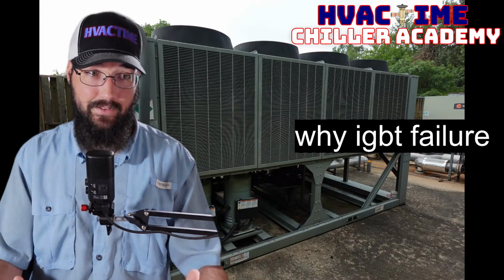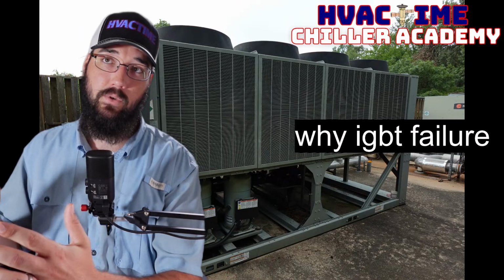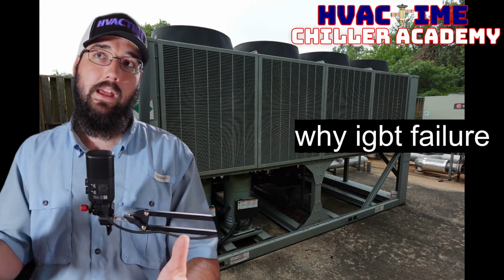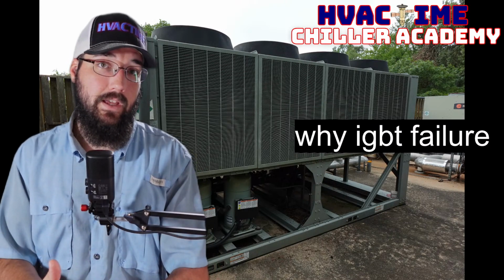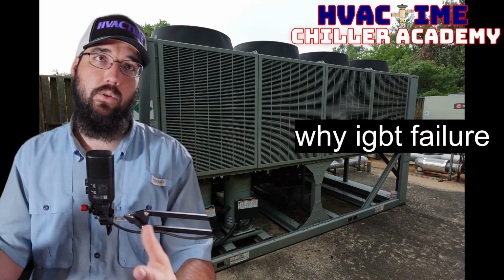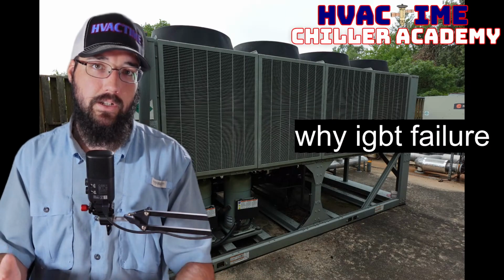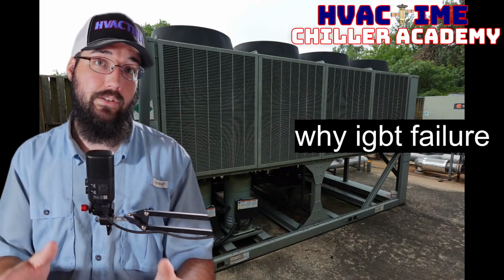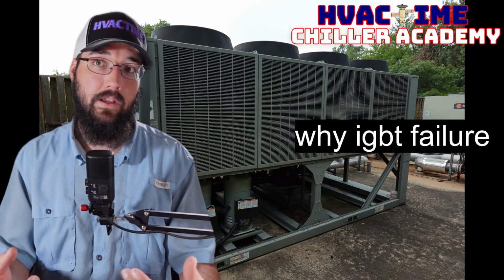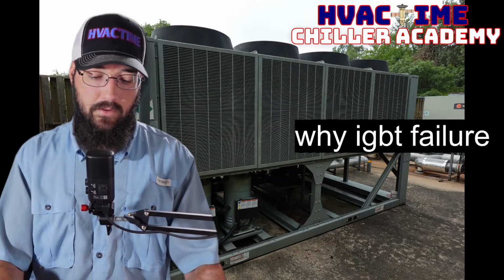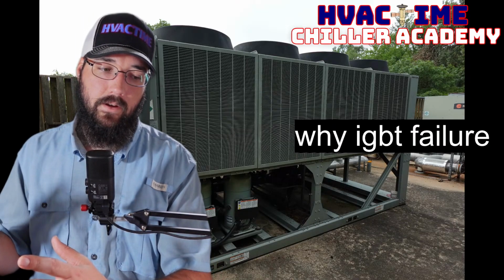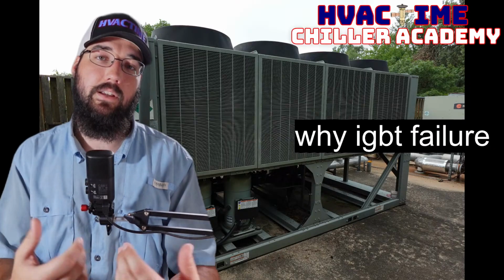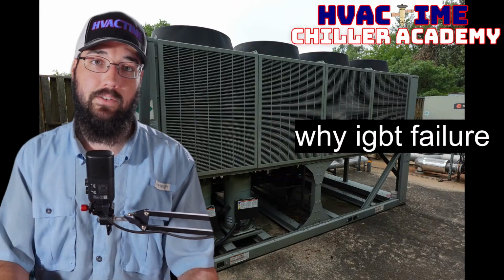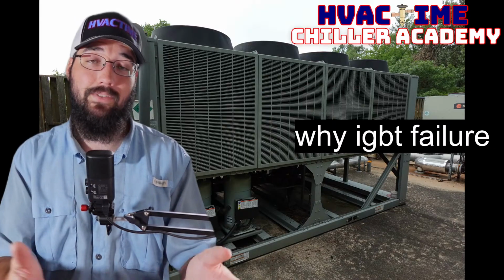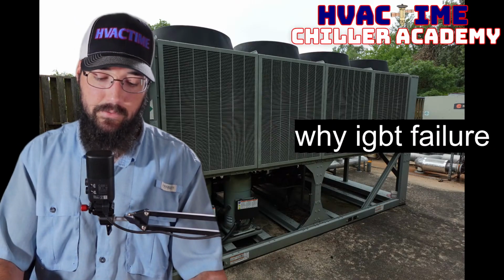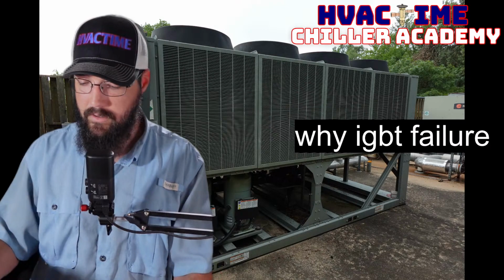Another way I've tested this is if I had a system with multiple compressors, I would sometimes swap the gates out. Or if I had multiple chillers, and I really thought this was the case and the customer wanted to know for sure, not just go off of my best assumption, then I would take one of the other IGBTs, put it in its place, and we would run test it and see if the compressor sounded better. If it did, we knew for a fact that that IGBT or that inverter needed to be taken care of.